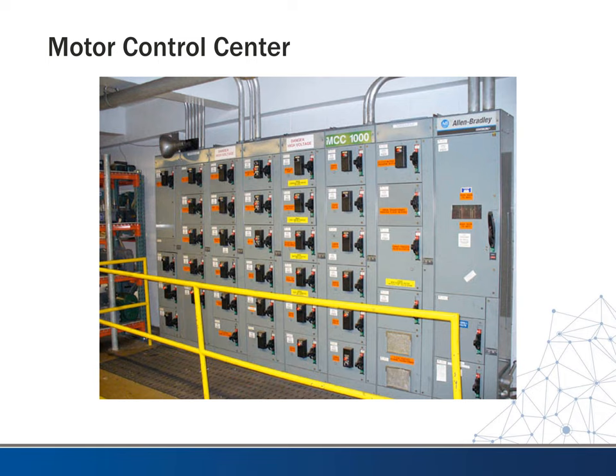So here's a picture of an MCC. You can see these are your buckets. You have a way to turn this off and on, but also some type of motor control module here. Some of them you can program right there in the bucket. Some of them just have connections, usually by Ethernet or some other BACnet connection, to go to some central processing area. So again, this is an MCC.